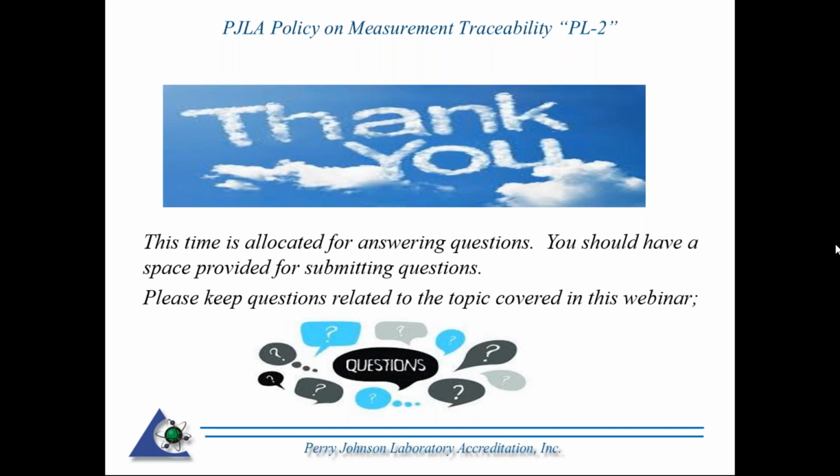And if you want to take a look, we did a webinar on the decision rule on our recorded webinar. That could be anything from simple acceptance, where you don't take it into account, on up to strict guard banding, 99% guard banding. So basically, the key thing with a decision rule, I know I'm going on to next month's topic here, is your customer has to agree to it. That's a requirement as per 17025. Your customer has to agree to your decision rule, and then that decision rule needs to be placed on the report.